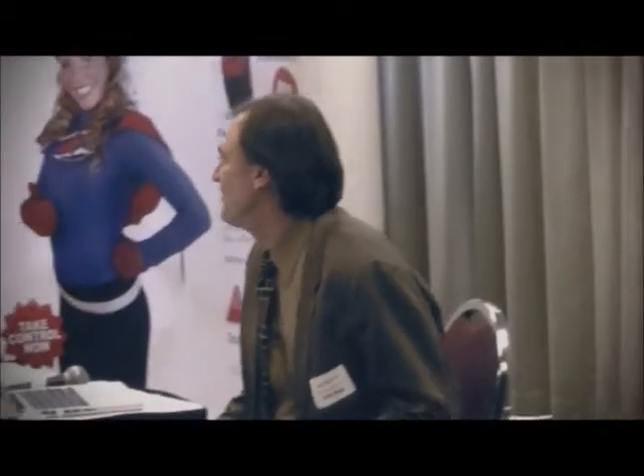I show this because it's cool. It's actually from a real application we did, from a site in a cold climate where North Country was cold. The customer was stunned. What the heck, you know, is that a lot of space heaters under desks? That's not what it was. Turned out they had electric humidifiers on their air handlers that people had just forgotten about. They'd been running so long, they weren't tied into the BAS, weren't managed, had their own little internal control, and would just fire off whenever they wanted to.